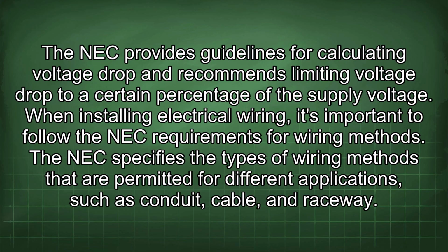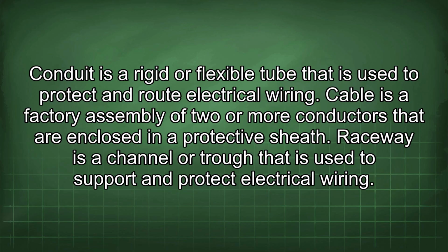When installing electrical wiring, it's important to follow the NEC requirements for wiring methods. The NEC specifies the types of wiring methods that are permitted for different applications, such as conduit, cable, and raceway. Conduit is a rigid or flexible tube that is used to protect and route electrical wiring. Cable is a factory assembly of two or more conductors that are enclosed in a protective sheath. Raceway is a channel or trough that is used to support and protect electrical wiring.